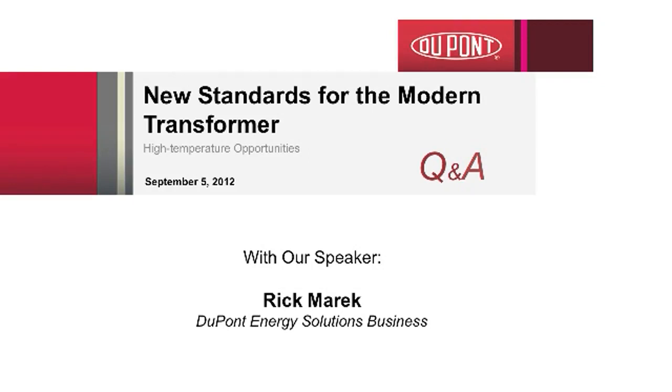Okay. A member of our audience has asked, does moisture affect Nomex the same way it might kraft paper? Well, no, it doesn't. Actually, Nomex will retain less moisture than cellulose in open air.